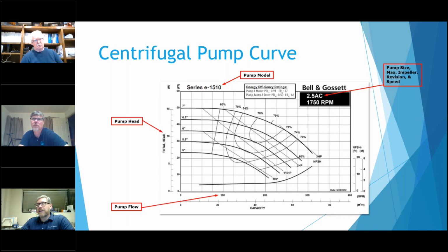Pump flow and head are in the same locations as the other ones. So this here is your impeller size. This one is going to have anywhere between a 5-inch and a 7-inch impeller inside of it. If you don't know what the impeller size is from the pump tag, it could be hard to tell where you're actually running. So you want to try to somehow determine what impeller size you have inside the pump.